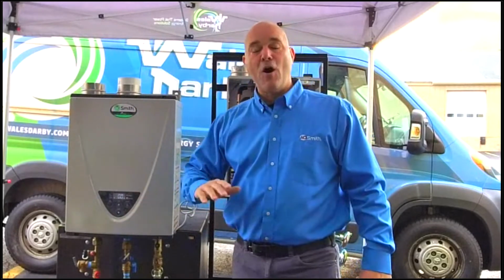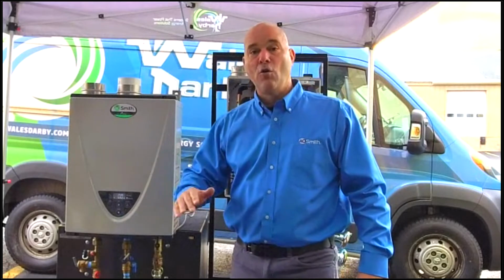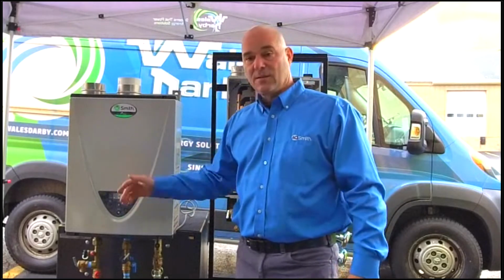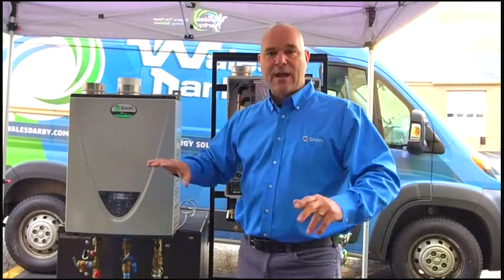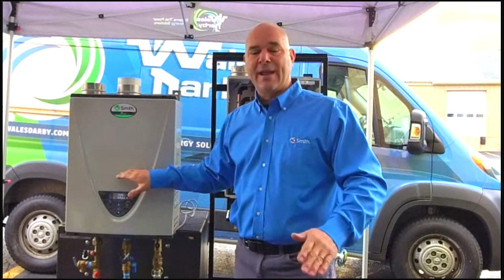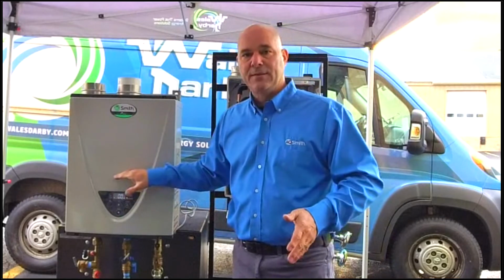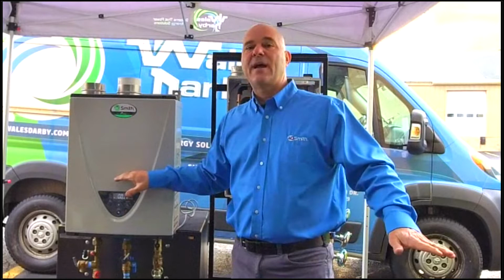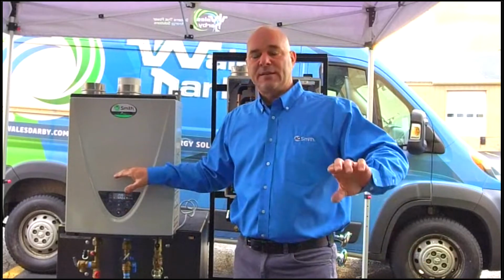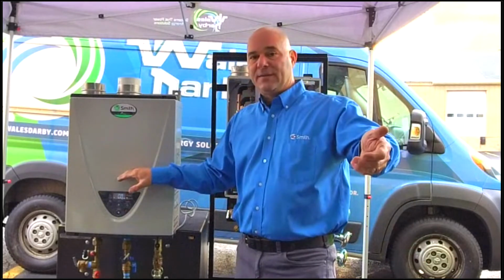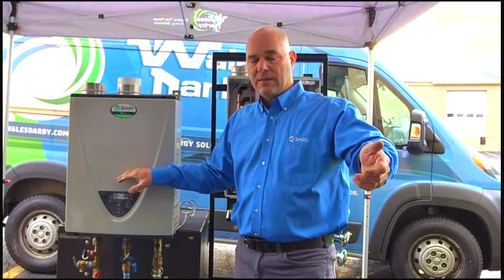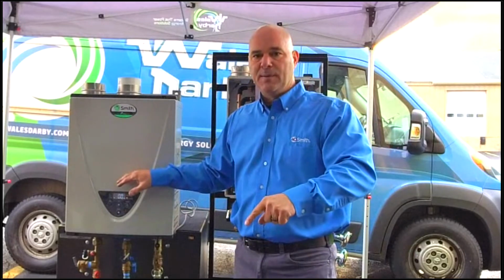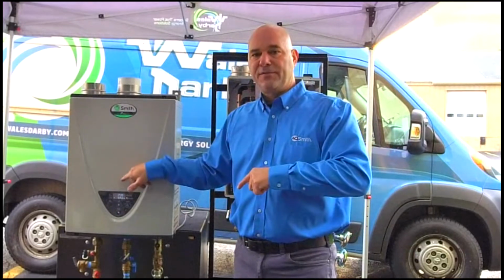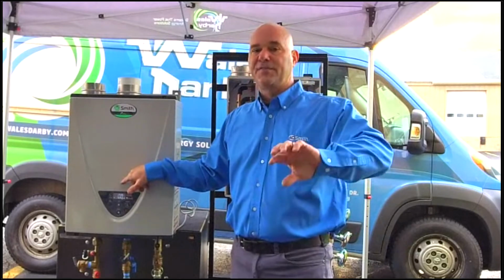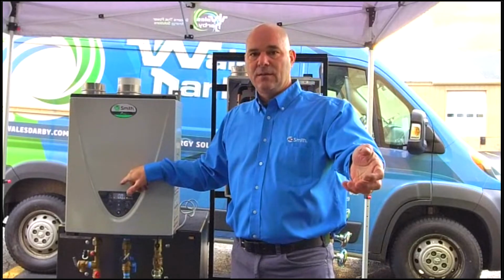I may not give you the volume that you're looking for. If you're overdrawing the ability of this, so let's say 70-degree rise, I'm giving you 5.4 gallons of hot water every single minute. And I can do that forever. But let's say I open up a 10-gallon a minute faucet. I will fill that 100-gallon tub, but I'm going to fill it at 5.4 gallons a minute. I'm not going to fill it at 10 gallons a minute.